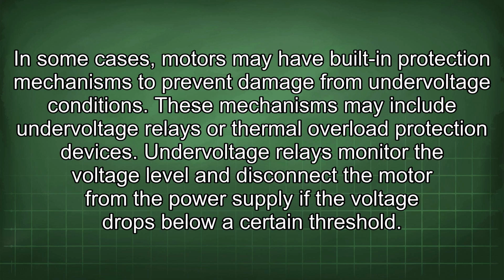In some cases, motors may have built-in protection mechanisms to prevent damage from undervoltage conditions. These mechanisms may include undervoltage relays or thermal overload protection devices. Undervoltage relays monitor the voltage level and disconnect the motor from the power supply if the voltage drops below a certain threshold.